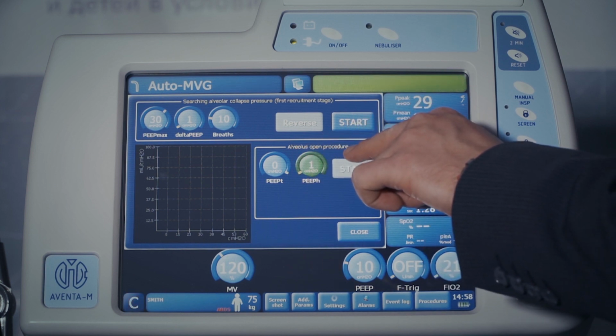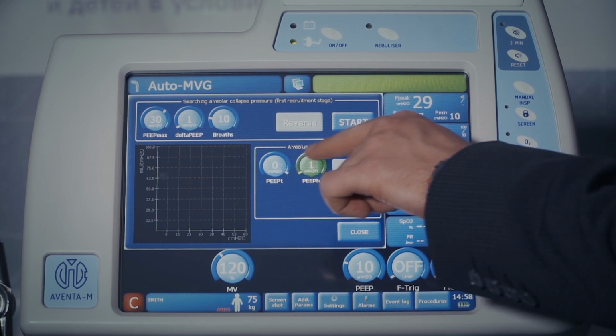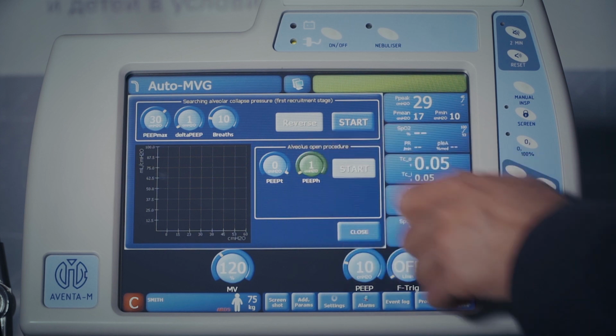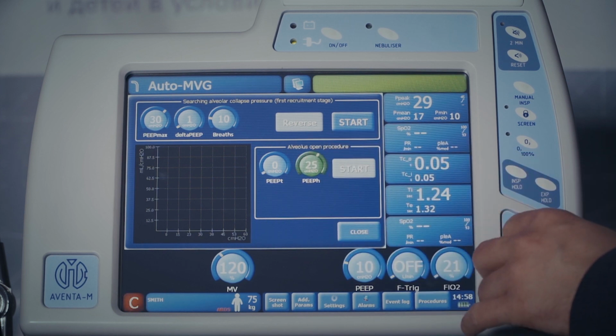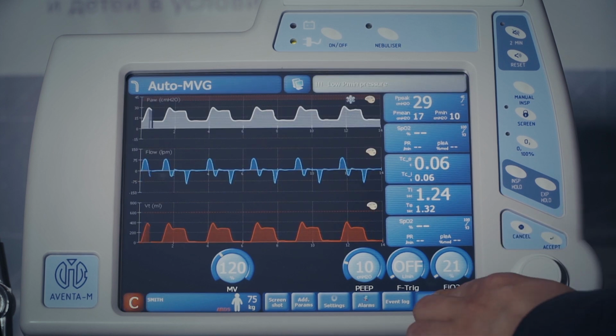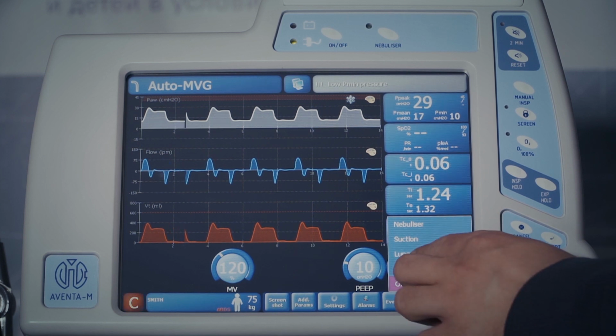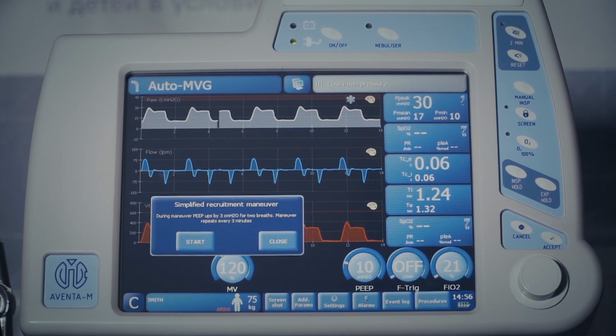Press Start. Upon completion of the maneuver, using 2 cursors, determine the maximum allowable level of PEEP and the minimum level following the shape of the obtained breathing loop. Enter the obtained values in Window Alveolus Open Procedure and start the second therapeutic stage by pressing button Start. For details of this procedure, refer to the operation manual. Simplified recruitment procedure is much simpler and constitutes in periodic increasing of PEEP level by 3 cm H2O for 2 breaths in a row.